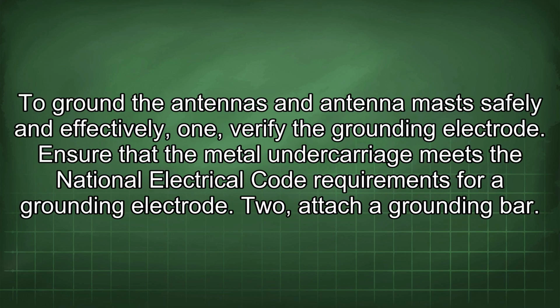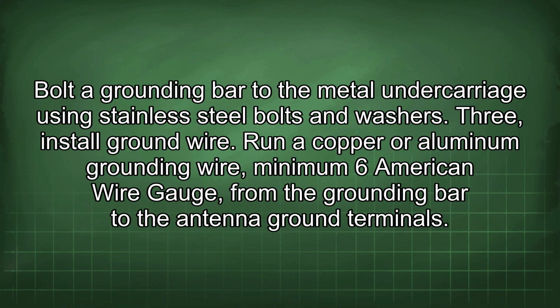To ground the antennas and antenna masts safely and effectively: 1. Verify the grounding electrode. Ensure that the metal undercarriage meets the National Electrical Code requirements for a grounding electrode. 2. Attach a grounding bar. Bolt a grounding bar to the metal undercarriage using stainless steel bolts and washers. 3. Install ground wire. Run a copper or aluminum grounding wire, minimum 6 American wire gauge, from the grounding bar to the antenna ground terminals.